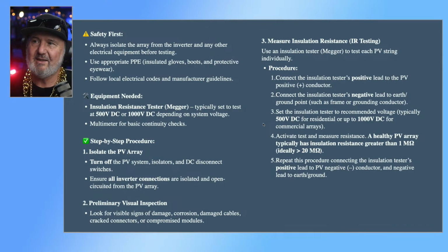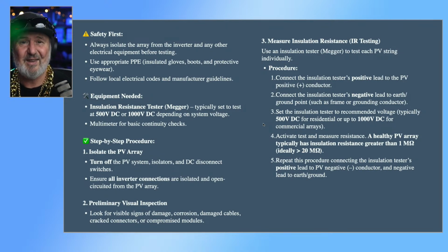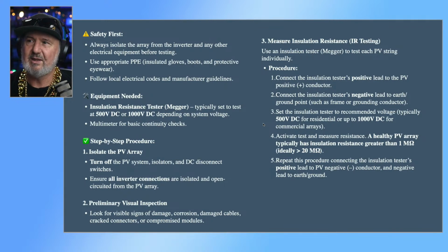The equipment is typically something people refer to as a Megger, which is a brand name, of course, but it's an insulation resistance tester. Now, people sometimes say, should I use 500 volts because, can panels take 1,000 volts? Yes, any panel tested to the latest IEC 61730 is actually tested to 2,500 volts, but then it's rated to typically either 1,500 volts or 1,000 volts on the manufacturer's label. So they can happily take 1,000 volts without causing any harm to the panel. You're going to need a multimeter as well for some basic continuity checks between conductive parts like the frame and the positive and negative output of the array.